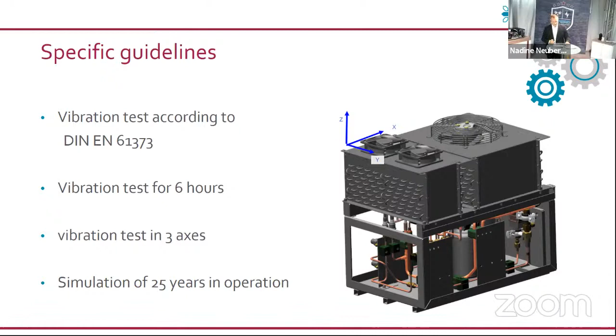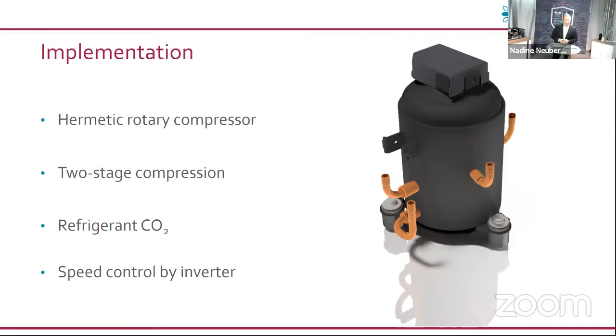Following, we are looking for a solution and an implementation. So we choose the Panasonic hermetic rotary compressor for this application. And this compressor works with a 2-stage compression. The refrigerant, as I told, is CO2. And this compressor is also speed controlled by an inverter.